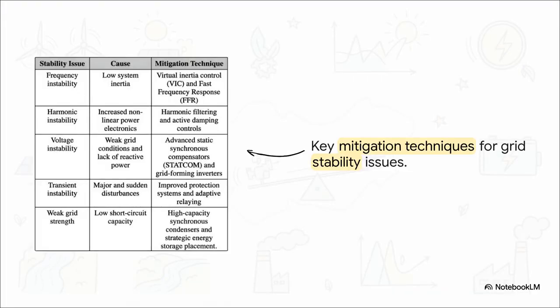If you map out these stability issues, you can see exactly how engineers are tackling these mathematical crises. For frequency instability caused by low inertia, the mitigation isn't going back to coal. No, it's advanced technology. We're using techniques like fast frequency response and something incredibly clever called virtual inertia control.